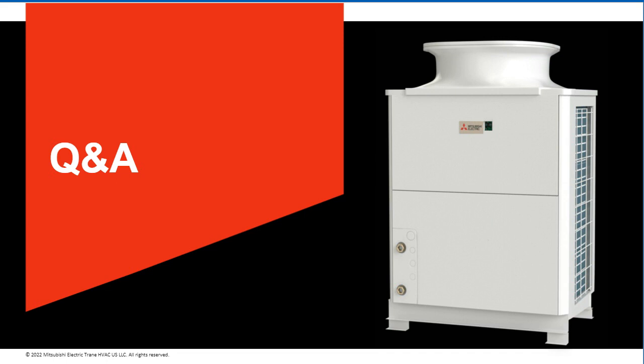Nope. All right. Is it possible to integrate the system with an existing gas boiler hot water heater? Is it possible for the two systems to work together seamlessly? Matt, I'll let you take that one. You've had more experience in that regard. Yeah, so it definitely is an opportunity, and the easy button would be to utilize the existing gas water heater, or even a new gas system, for that swing tank usage, and then you would use the hot water heat pump to do a lot of your generation work as much as possible. We do have examples of that, where people want to use both fuels or they still want to test the waters with this to say, hey, we're not ready to jump in 100%, but we want to peel some of the load off our building from gas use, and we've done that in some cases already today.